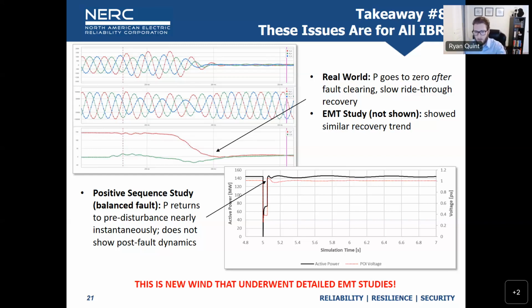Taking the positive sequence model pulled right from the base case, the one submitted in the latest dynamics files available, the plant snaps right back up to active power as soon as the fault clears and settles pretty quickly. This response really should look like that. This is only hundreds of milliseconds, 200 milliseconds per division, so it wouldn't be something drastic, but it would be a recovery that looks something like this, not what you see here. It's just one example, but even though a detailed EMT study was done, these models don't match each other. They weren't benchmarked against each other, so this model is wrong and it needs to be updated.